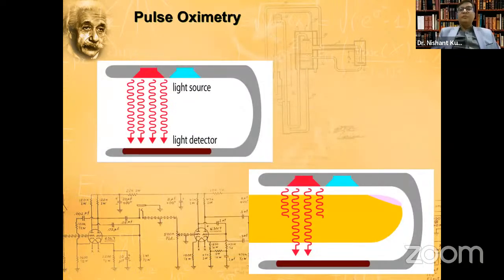So how do we measure it? How do we know how much is oxygenated hemoglobin and how much is deoxygenated hemoglobin? Now we all know this is the usual cut section of a pulse oximeter. It contains a light source. Actually, it contains 2 light sources and a light detector. One is the red light source and one is the infrared. We'll be talking about it later. It emits a light with a fixed wavelength, which is detected by the detector here. This is called transmittance because the light is being transmitted and read by the other electrode here.